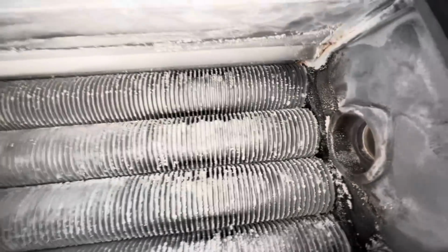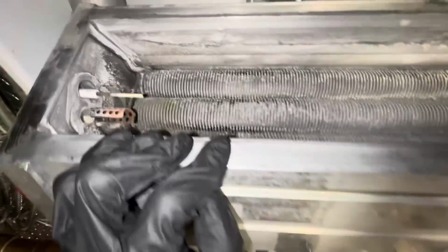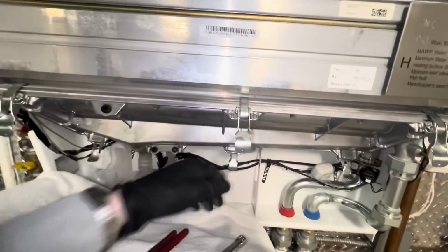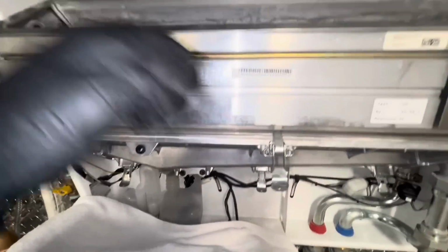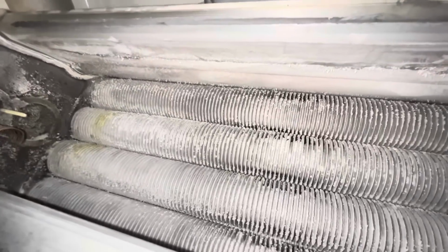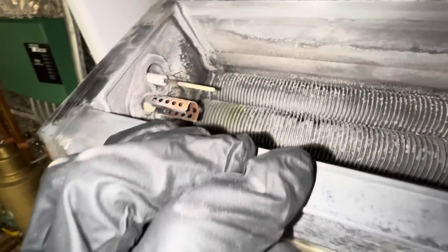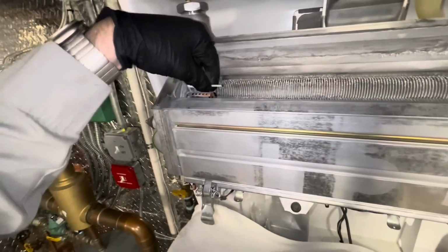That's a lot. I'll wait for this section to cool a bit before I pull it off to take a look. I'll dry vacuum everything first, then go in with some water, force some water through, pull off our flame sensor, get that cleaned off. But the flame sensor and igniter still look okay.